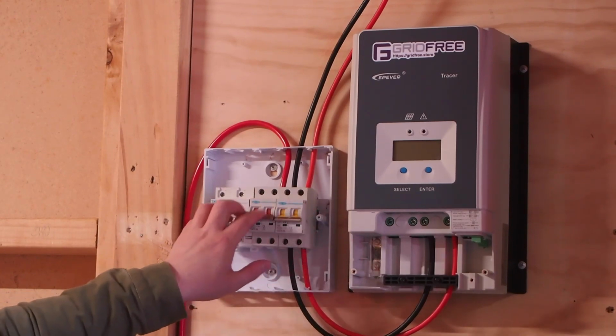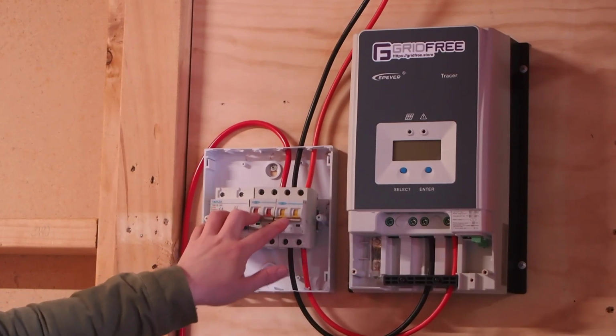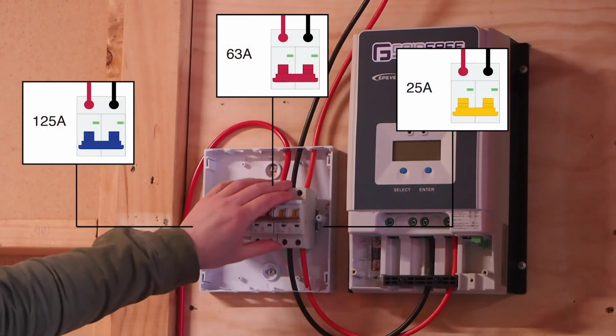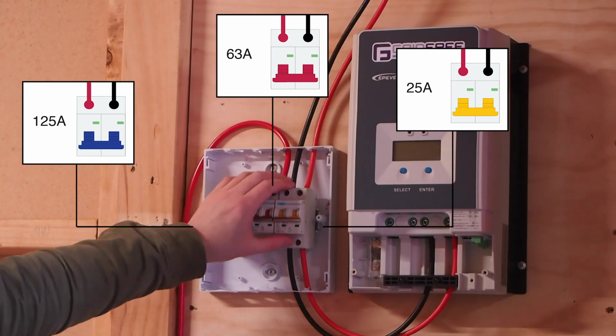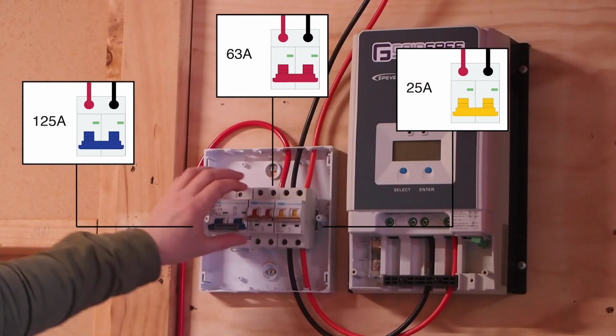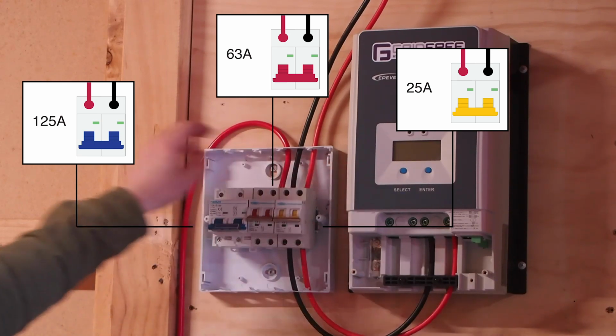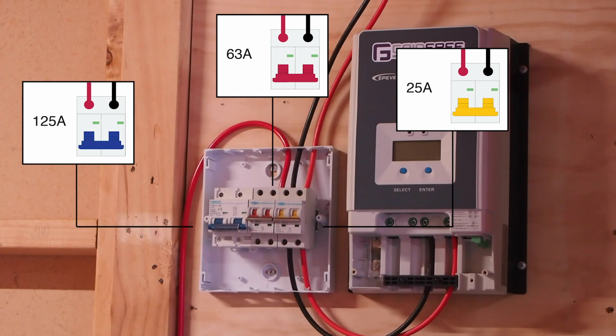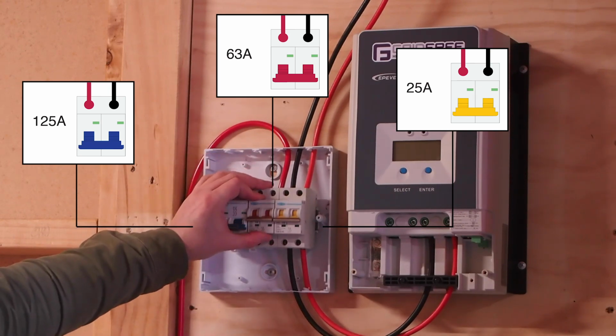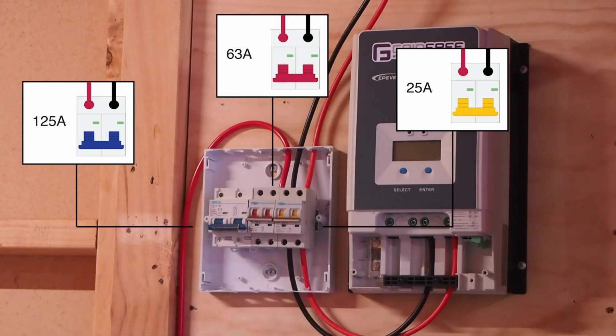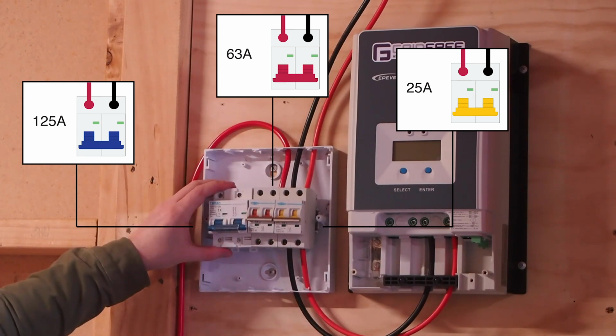Making sure that while we're working on this, all the circuit breakers are in the down position, which is the off position. The circuit breaker that we use for the solar panels, this one here, is the 25 amp circuit breaker. This one next to it, that we're doing from the charge controller to the batteries to charge the batteries, is a 63 amp. And the one that's going to run between the batteries and our inverter is 125 amp.